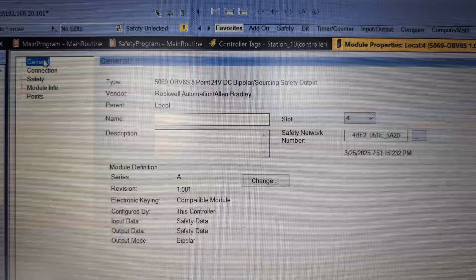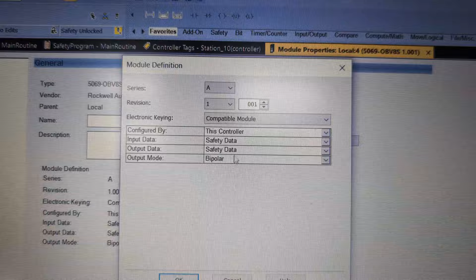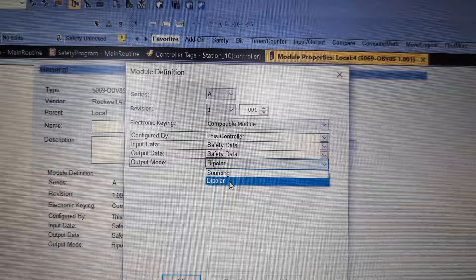But what I didn't realize is you have to go up to the general tab, and if we go to change, right here it defaults to sourcing, and we need to go to bipolar mode. I had to thank my buddy Jeff Kuiper with Full Circle Automation for telling me that. He said, no, you can't do that, you've got to put the whole module in bipolar mode. I said, well, I'm using a lot of them as single channels. He said, yeah, that's perfectly fine.